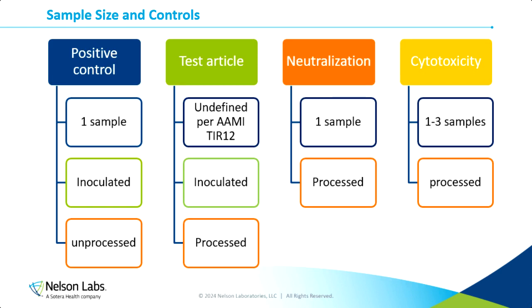The other update in TIR12 that I want to go over is that the test article sample size is now undefined in this document. It did previously state to evaluate a minimum of three test articles or test replicates and one concurrent positive control. That verbiage has now been removed from AAMI TIR12, and it's left as undefined. It doesn't give any further guidance on how to define a sample size, or that you need to justify what sample size you use. But it is important to note that the verbiage has been removed.